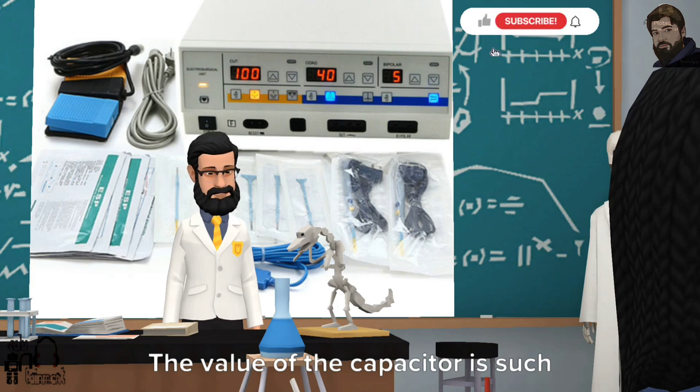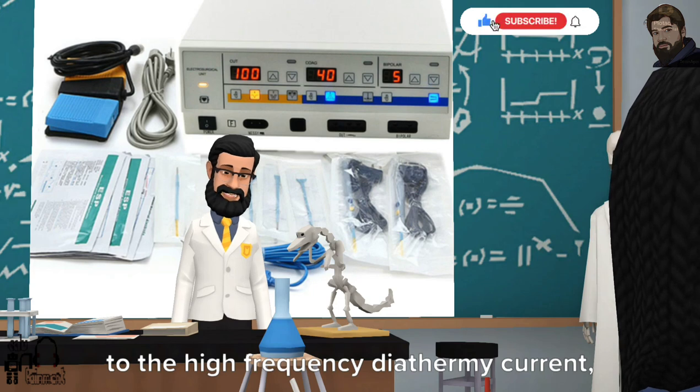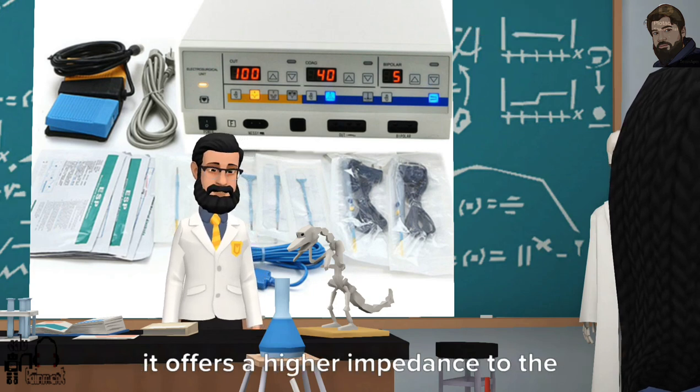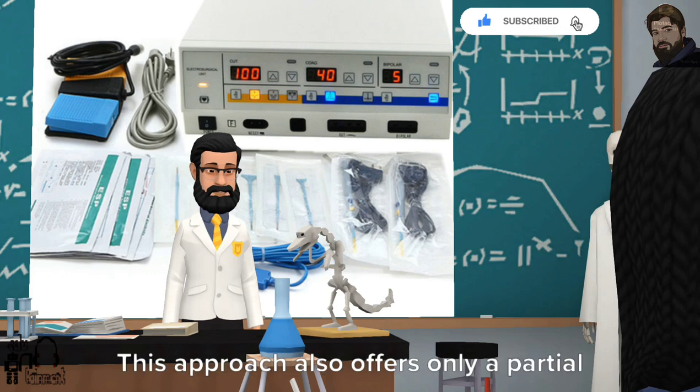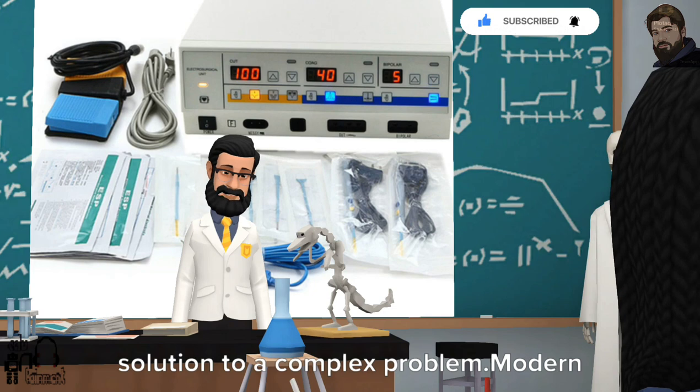The value of the capacitor is such that while providing a very low impedance to the high frequency diathermy current, it offers a higher impedance to the mains frequency. This approach also offers only a partial solution to a complex problem.